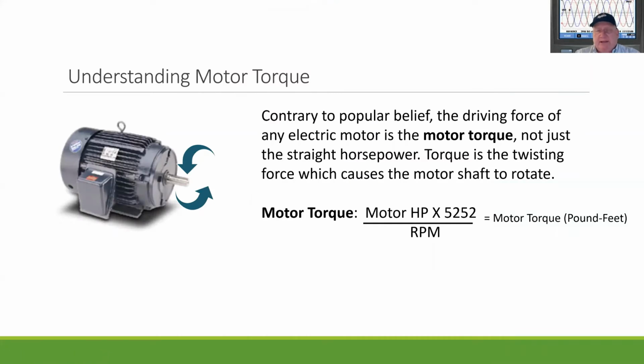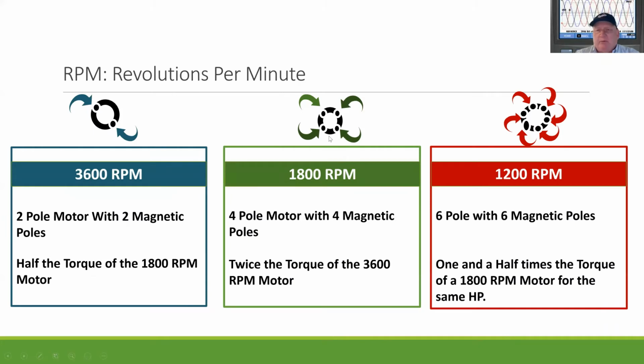The other area that we want to talk about is the understanding of torque and power, and Rob's going to go into this more later. What happens when you have a 4-pole machine? Here, as I showed in some of the stator windings, they have basically 4 magnets, and so it has twice as much torque as a 3600, which is basically a 2-pole machine. Cheaper to build. These are 1800, but even some of the older ones used to be 1200, where they would put 6 magnetic poles in there, and that would give you a lot of additional torque, like 1.5 times the torque of an 1800 RPM motor.